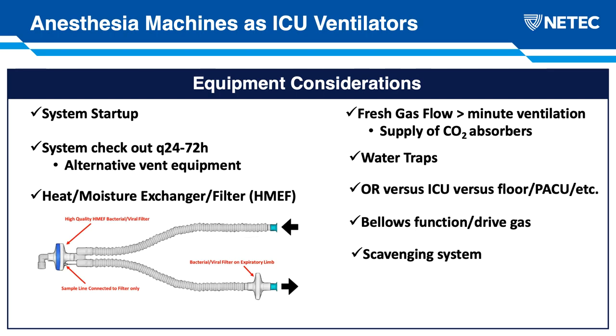We talked about the HME or the HMEF, this heat moisture exchanger. The F indicates there's a bacterial and viral filter. We recommend that 2 of these are in place. The full HMEF would be closest to the patient. We'd want to make sure that our sample line for end-tidal CO2 monitoring was on the machine side to keep the gas bench clean. And we put an extra bacterial and viral filter on the expiratory limb where it meets the machine to keep the machine internals clean.